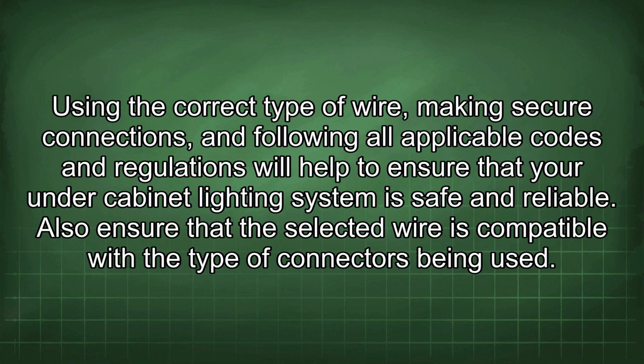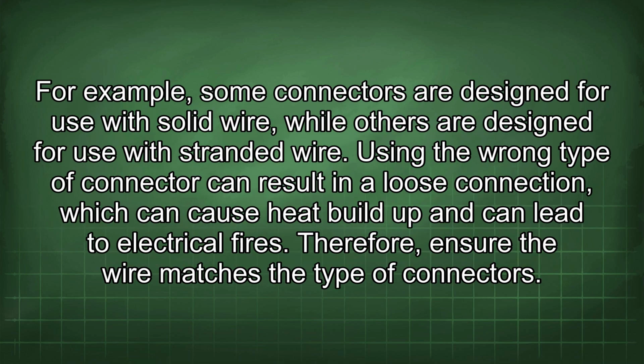Also ensure that the selected wire is compatible with the type of connectors being used. For example, some connectors are designed for use with solid wire, while others are designed for use with stranded wire. Using the wrong type of connector can result in a loose connection, which can cause heat build-up and can lead to electrical fires. Therefore, ensure the wire matches the type of connectors.